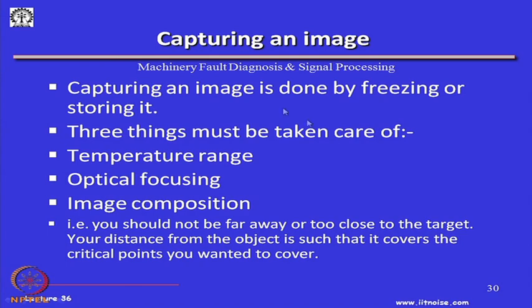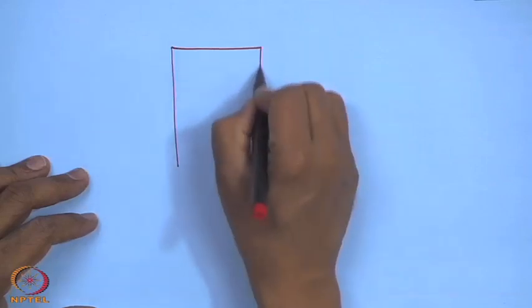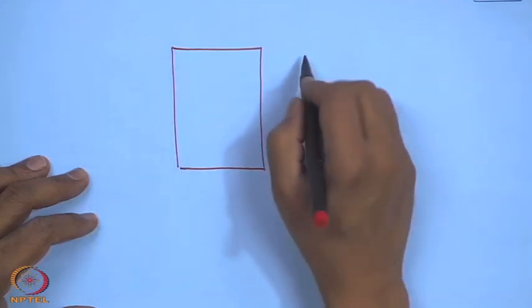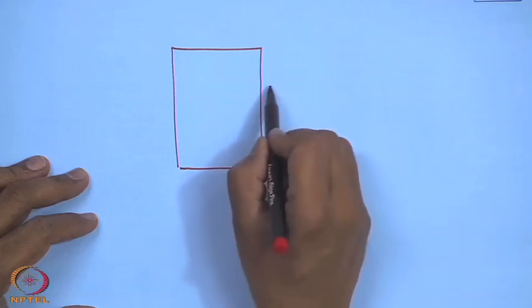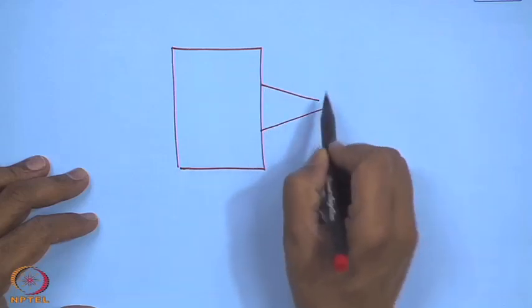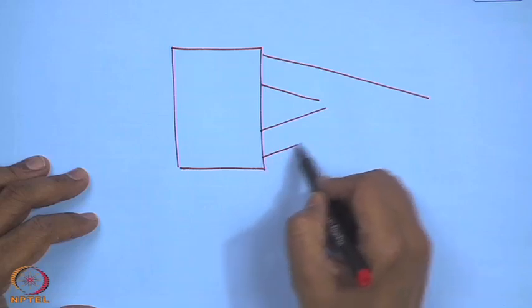So essentially, three things must be taken care of while doing thermography: the temperature range, focusing, and the image composition. You should not be too far away or too close to the target. Your distance from the object should be such that it covers the critical points you want it to cover. It depends on the focusing area and the depth of coverage. If you are close by, you can only get this; if you are far off, you get this. So it depends on this distance and this area.